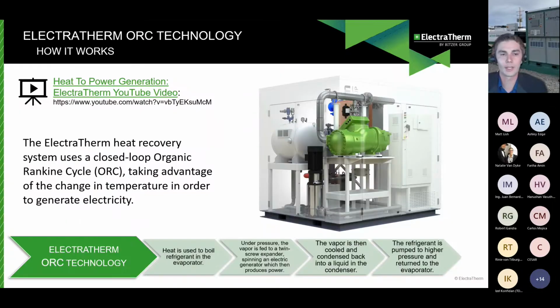So how the technology works, it's actually a very simple cycle. What we're doing is using heat to boil refrigerant rather than hot water. So it's similar to steam power generation of yesteryear, only we're using an organic refrigerant in the evaporator. So our refrigerant is non-toxic or low toxicity and non-flammable. And we're heating that with your heat source. So under pressure, that's going through the expander that we talked about earlier. That's very similar to a refrigeration compressor, which spins a generator and produces power. Now, this is a closed loop system with this refrigerant, so that vapor is cooled and condensed back into a liquid, and then we pump it to a higher pressure and return it to that evaporator. We return it to that heat source.